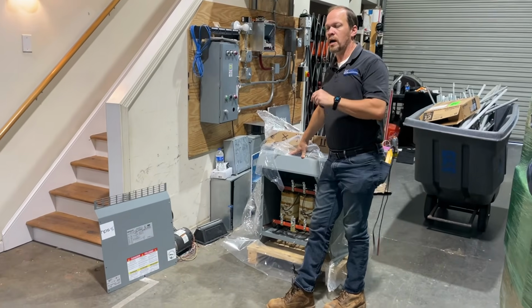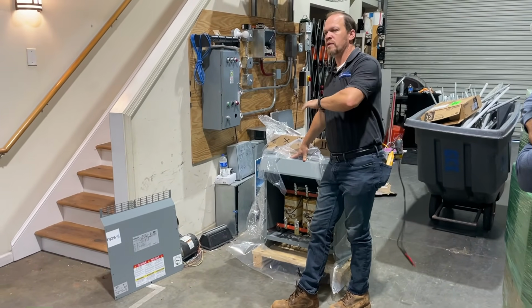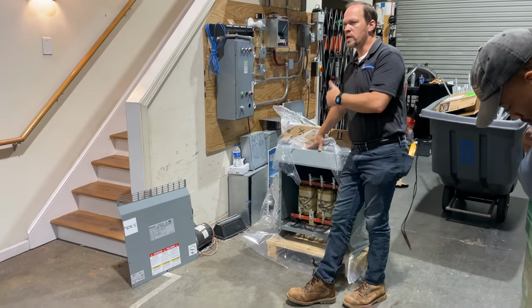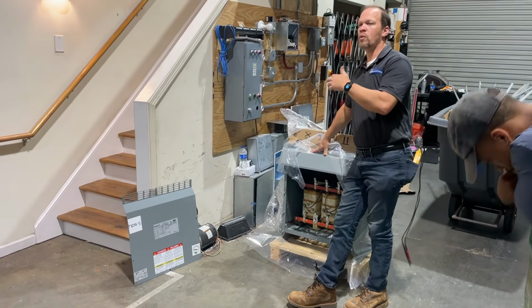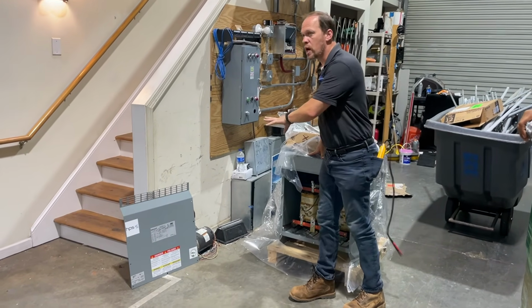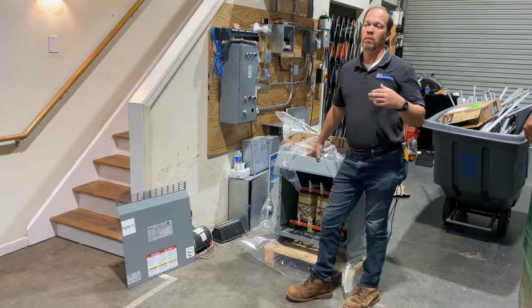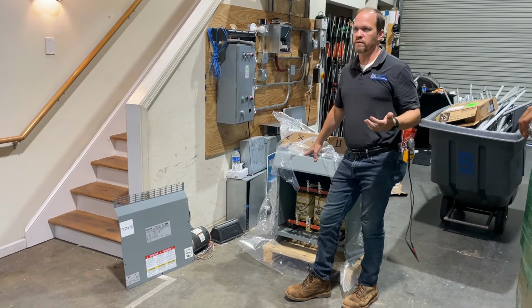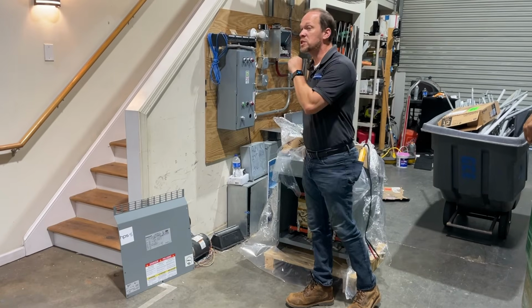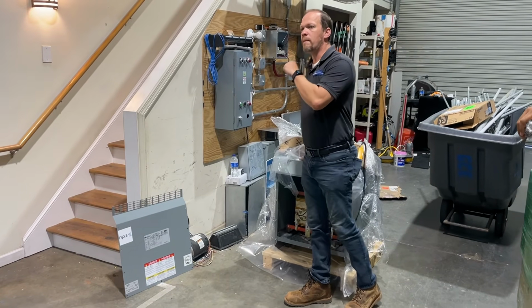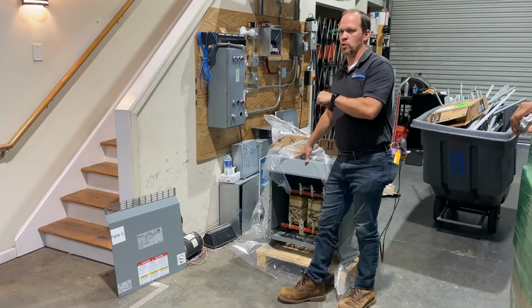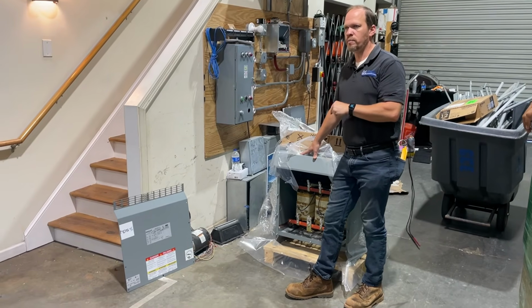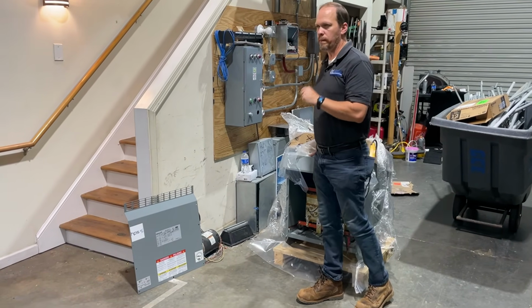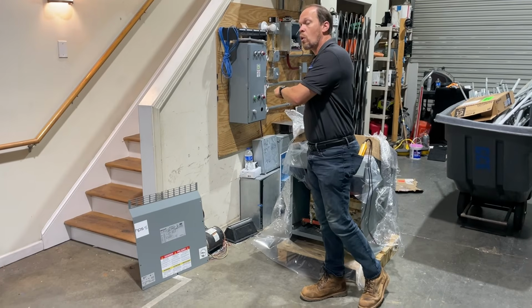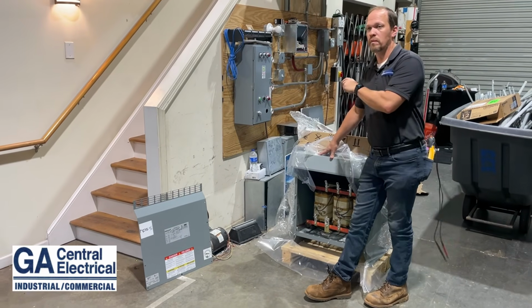So that's the only difference, you guys just make sure you understand this part of it. The hooking up is the easy part. Understanding where you got to make those differences, where you got to use transformer taps, where you got to address the voltage differences, and specifically where you got to bond the neutral -- that's a really, really big important step, where you got to bond the neutral or corner ground the high voltage side.